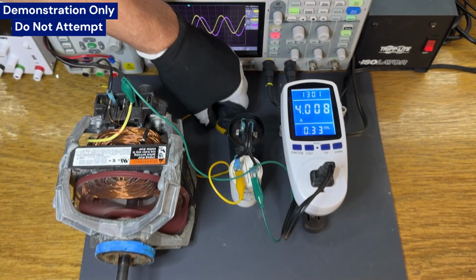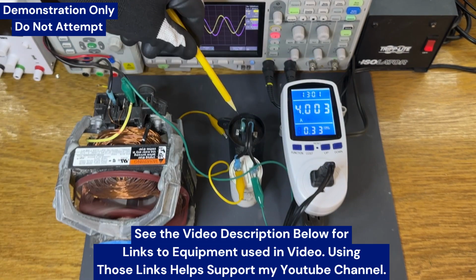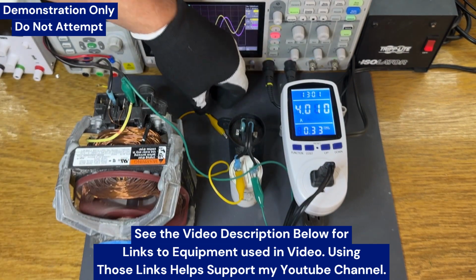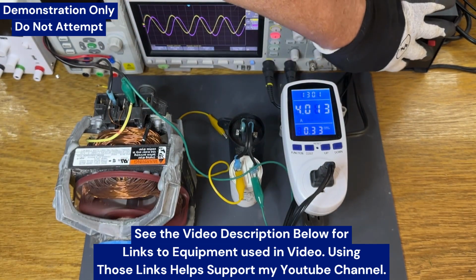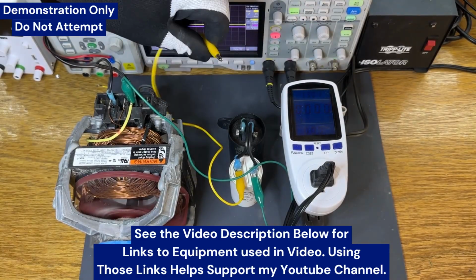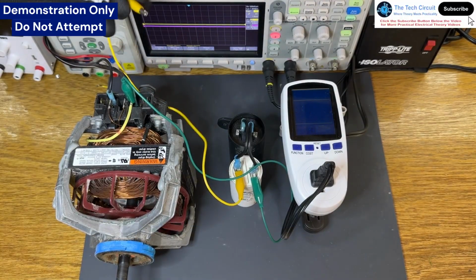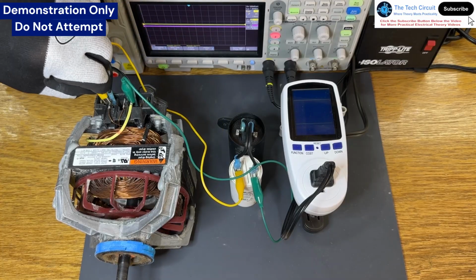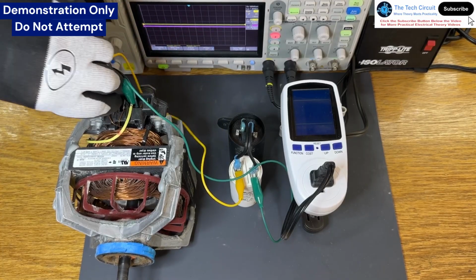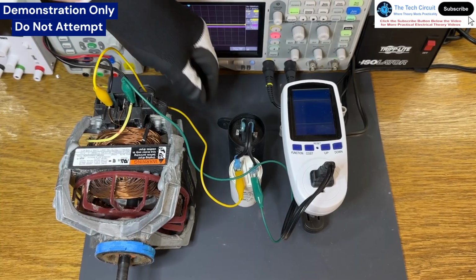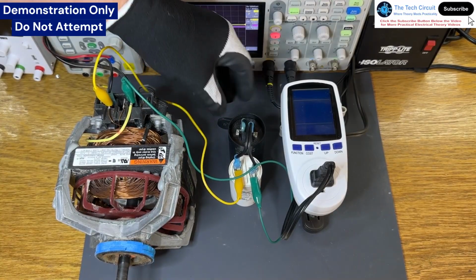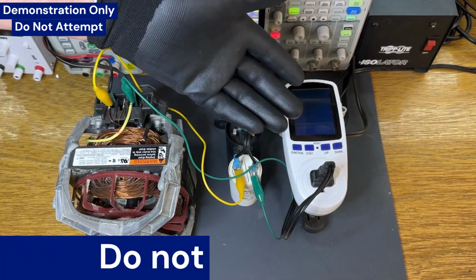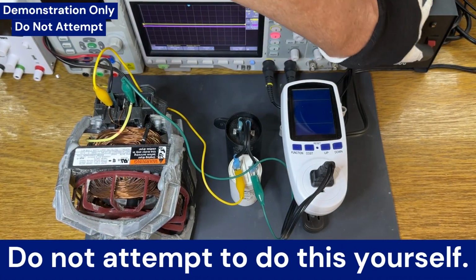I've got a few motor run capacitors on hand, so I'll combine them in parallel to get as close as possible to that value, which turns out to be about 93 microfarads, within 10% of our calculated value. This won't get us to a perfect power factor, but it'll get us really close, and we'll get our final current draw to less than 1.5 amps. Now I'll wire this capacitor bank in parallel with the motor. Again, this is for demonstration purposes only. Do not try this at home.